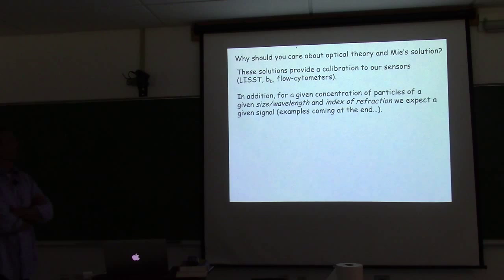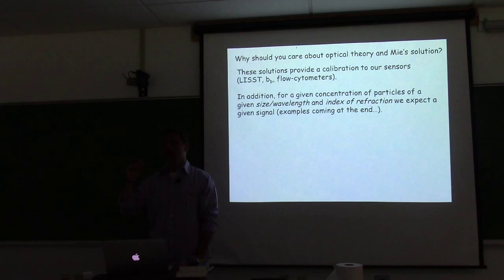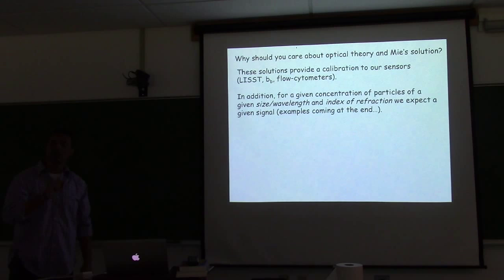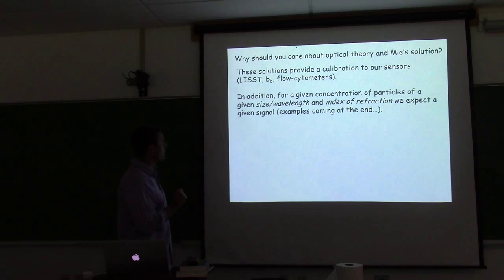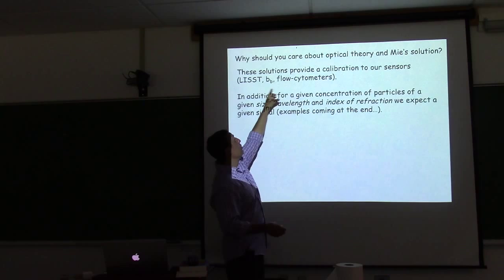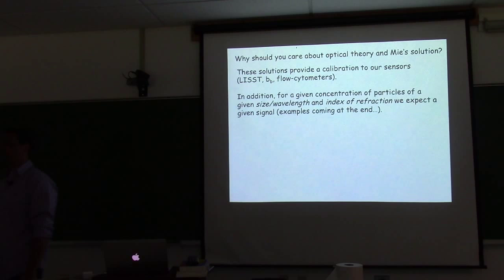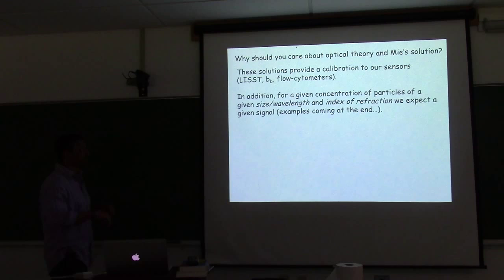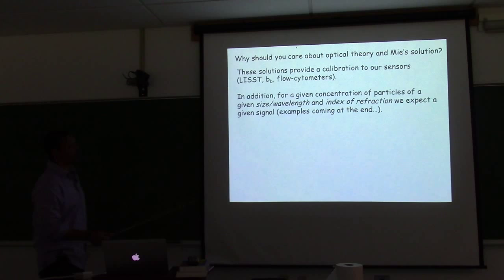Why should we care about optical theory and Mie solution? When we calibrate the instrument with beads, we go to Mie theory to tell us what we should expect for a given concentration of beads of a given size and composition — what is the scattering we should expect from the suspension. Then we can put them inside our instrument, whether it's a test chamber, a bucket, or a flow cytometer, run the beads through, and use those to calibrate our instrument. For this, people use expensive NIST-traceable beads so they know exactly the size distribution; they're spherical.